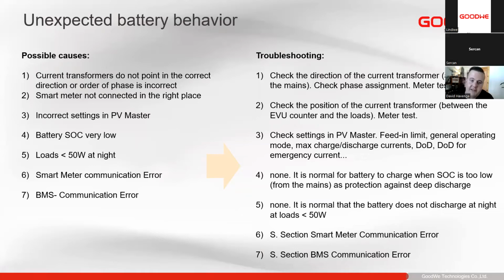Incorrect settings in PV Master, like I said, we need to double check and make sure that our economic mode timer is not set. Then, when the battery SOC is very low, especially in Europe or anywhere in the world, when we have no PV for a long time and our inverter is set to general mode, so we'll only charge from excess PV that's available.